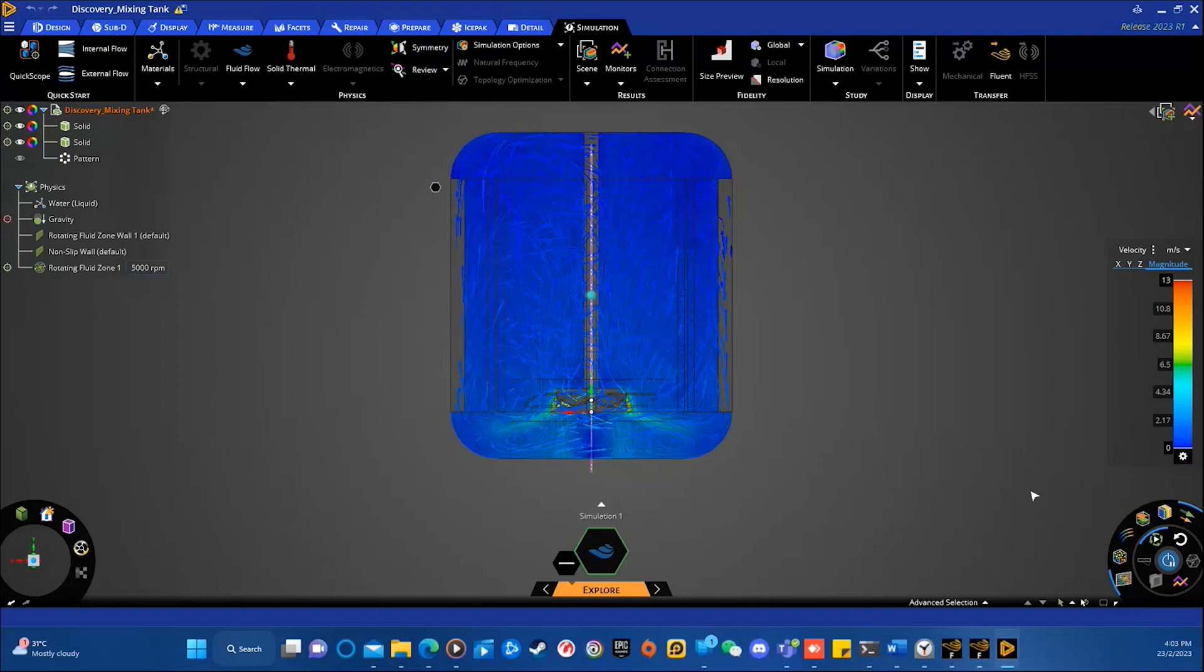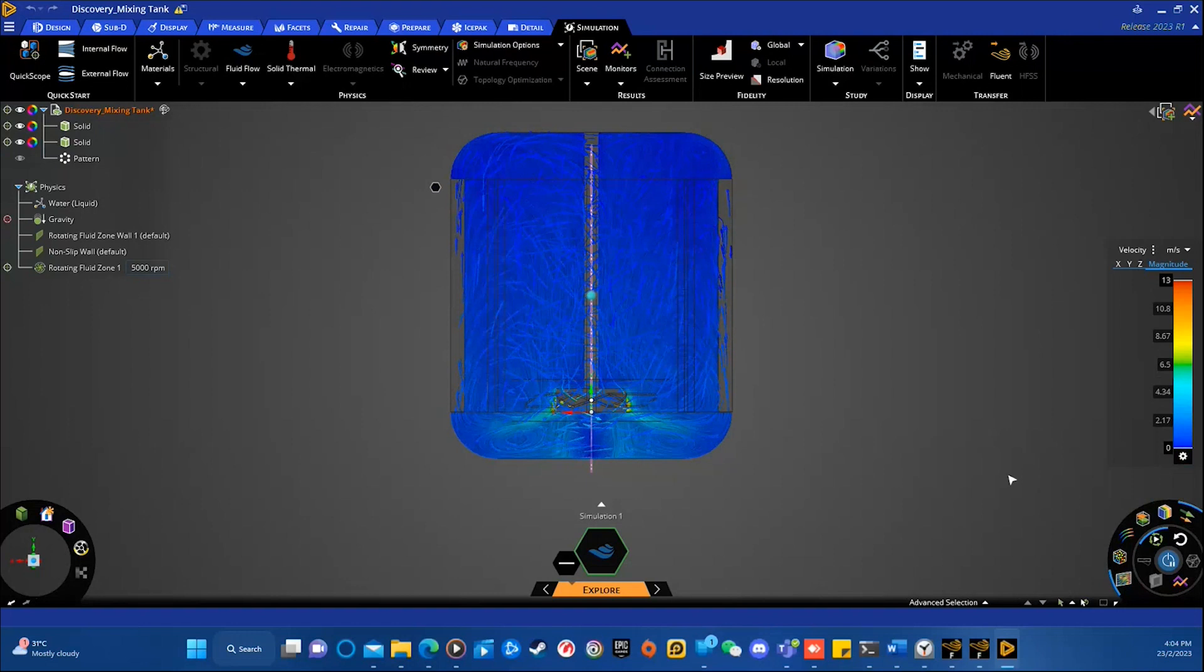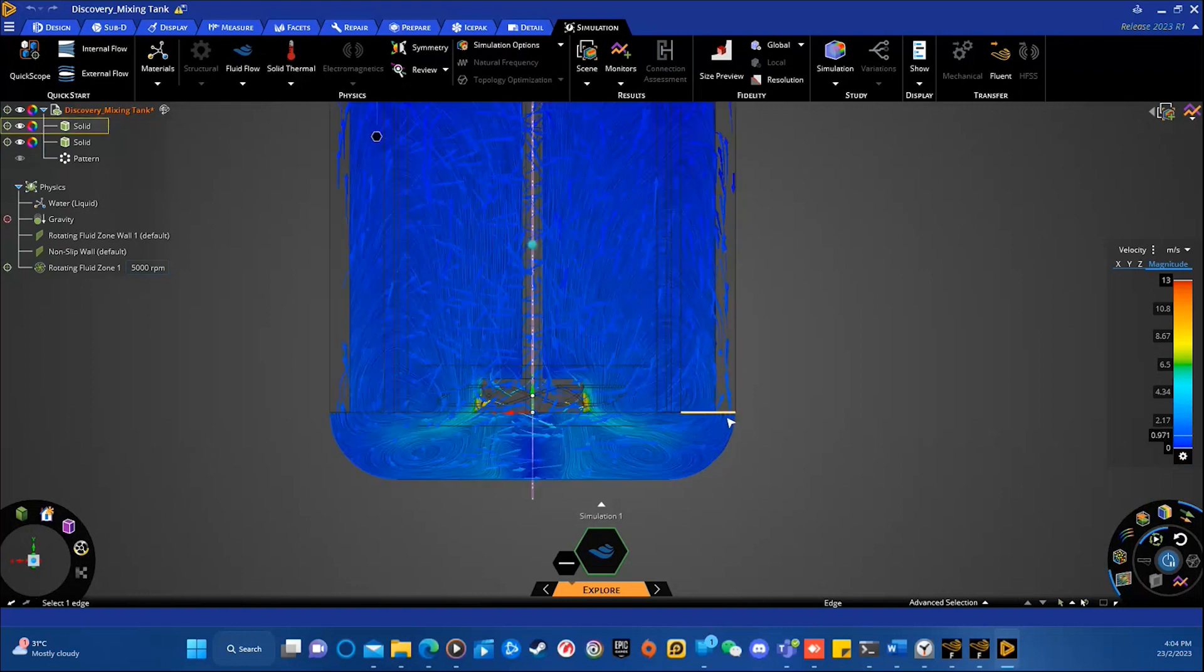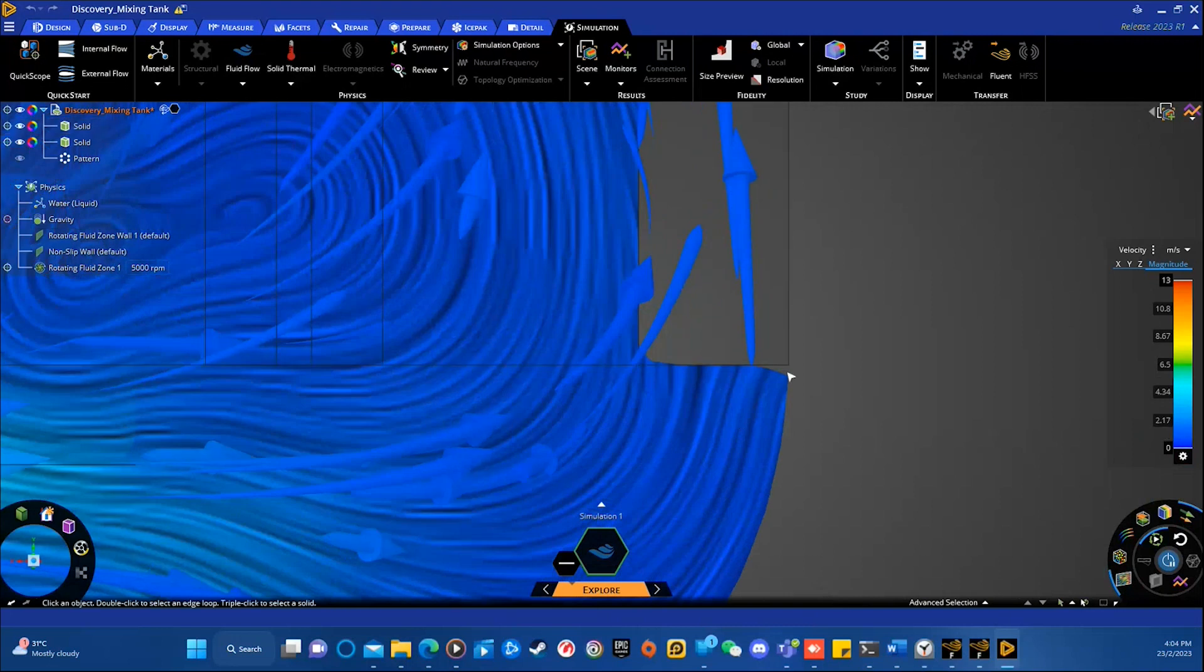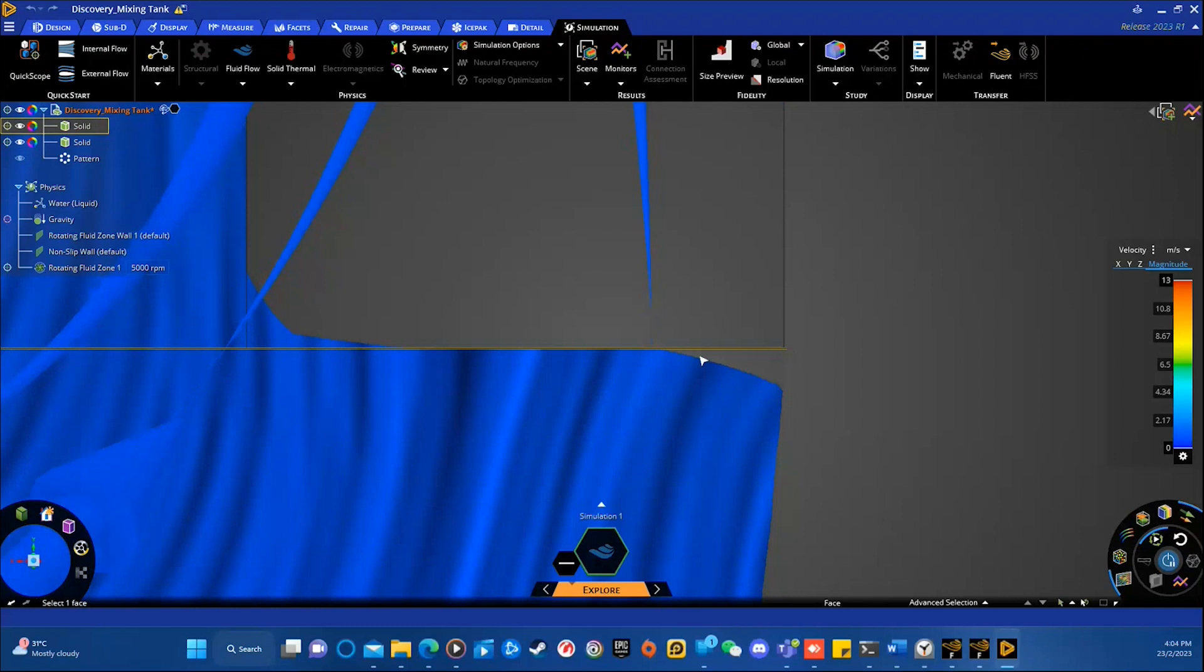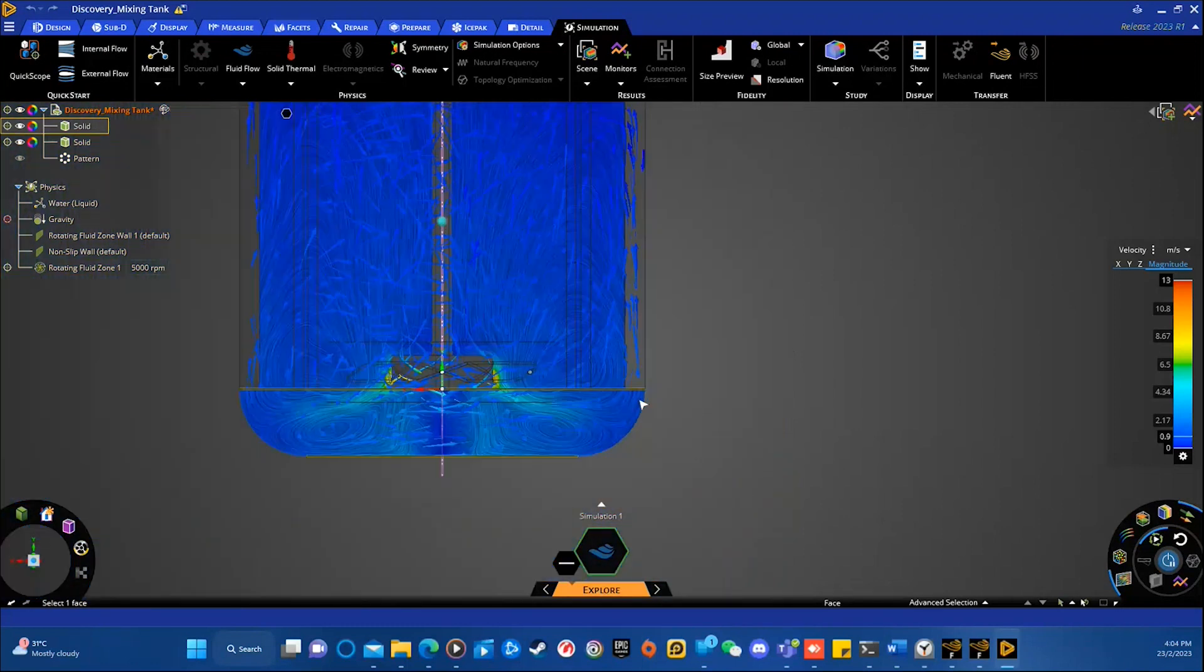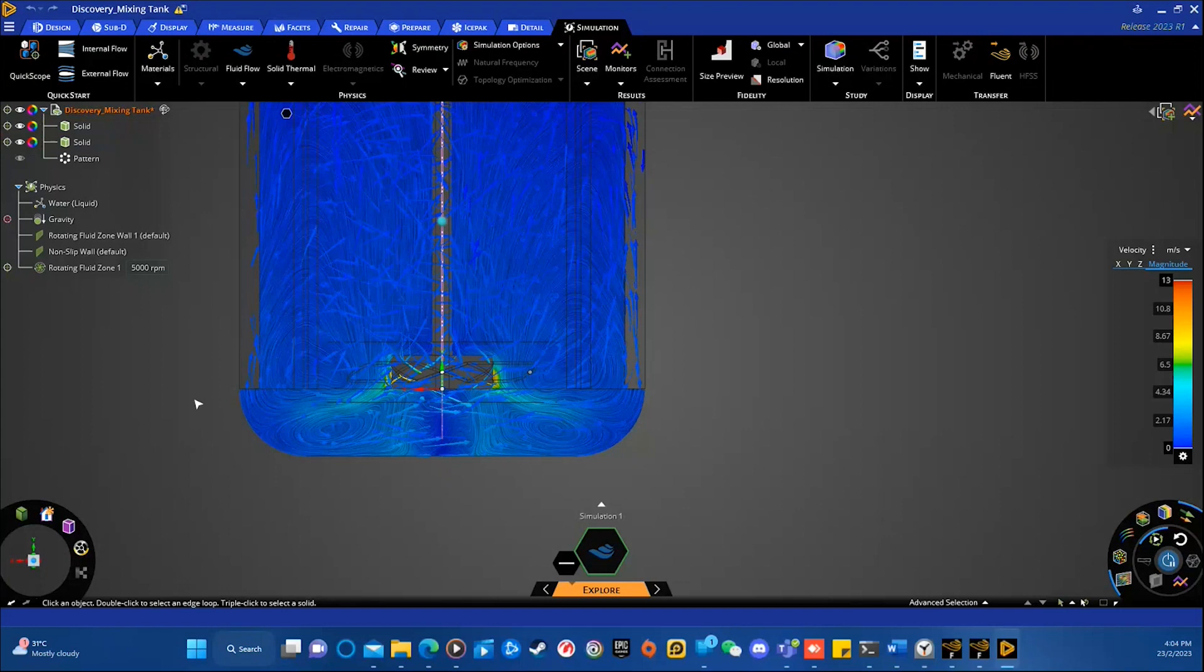These tools can help you to optimize your design and improve the performance of your system. For example, you may use the vector visualization to see if there are any areas of high turbulence or recirculation that are reducing the performance of your system. Alternatively, you can use the line-integral convolution to identify the location and size of vortices, which can have significant impact on the efficiency. As you can see from here, there's actually dead zones between the baffle and the lower sections. So some changes have to be made to the models to increase the performance.